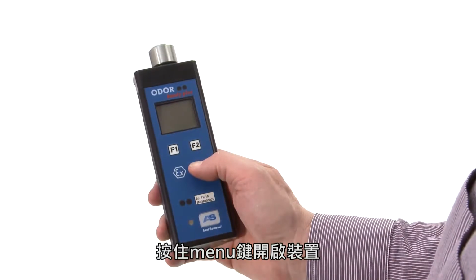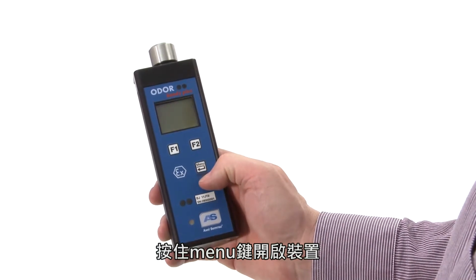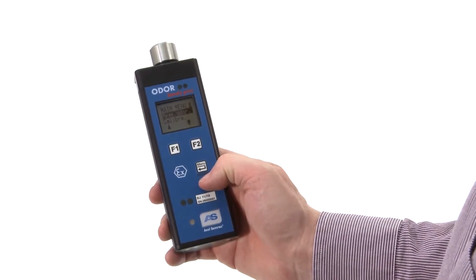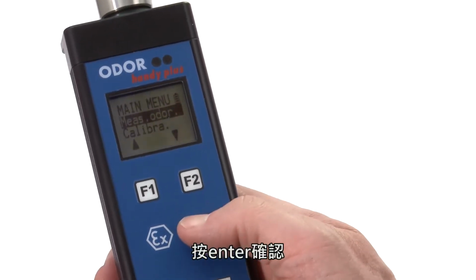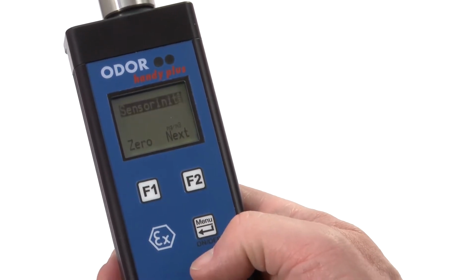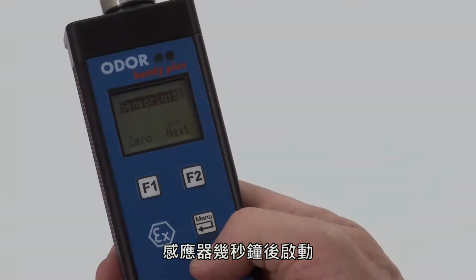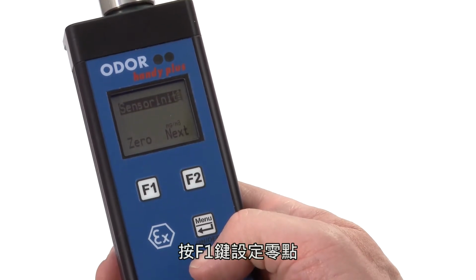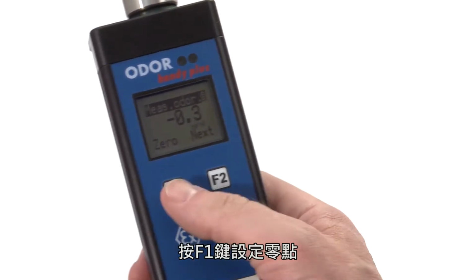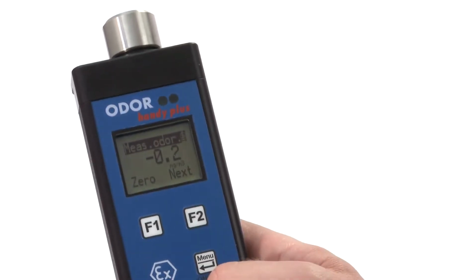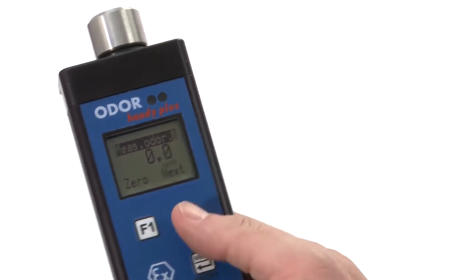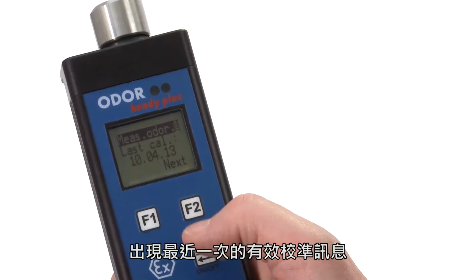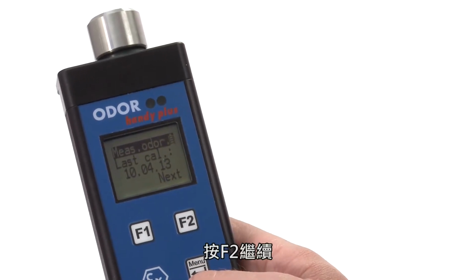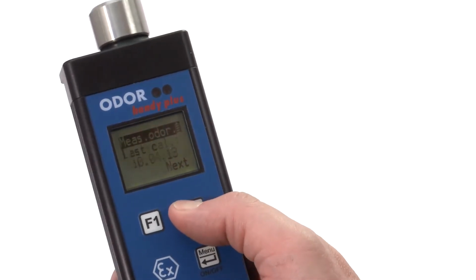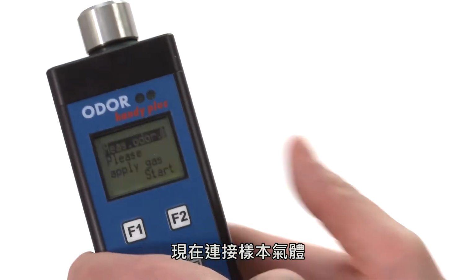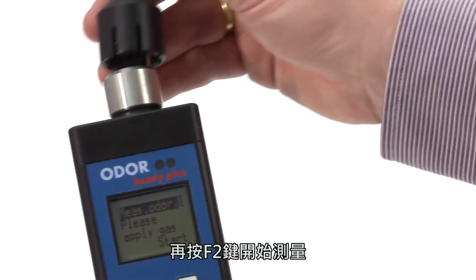Switch on the device by pressing and holding the menu button. Choose Measurement in the menu and confirm by pressing Enter. The sensor initializes for a few seconds. You can set the 0 point by pressing F1. Press F2 to continue. A message about the last valid calibration appears. Press F2 to continue. Now connect the sample gas and then press F2 to start the measurement.